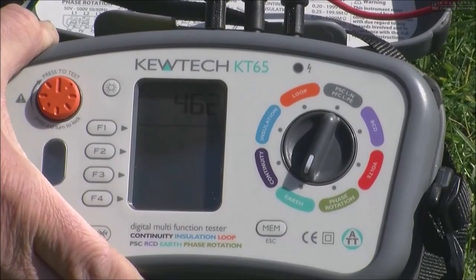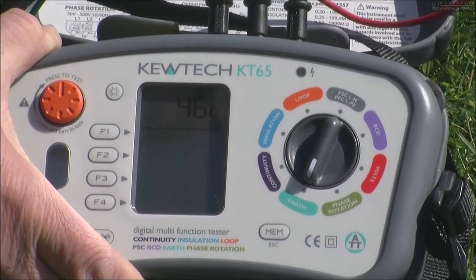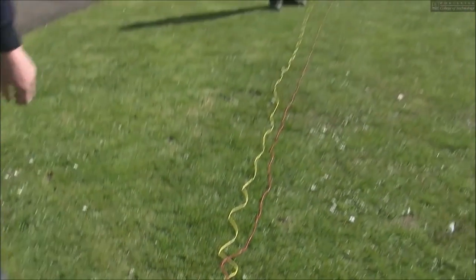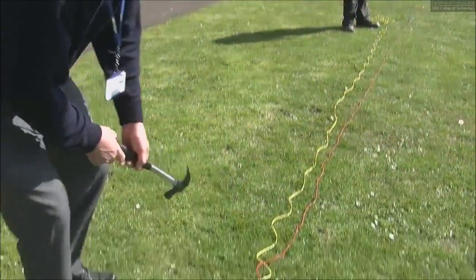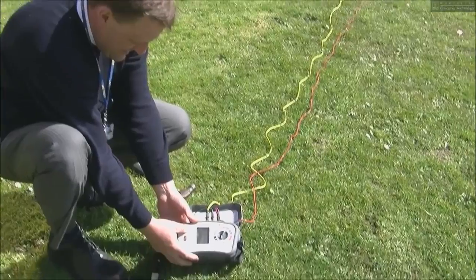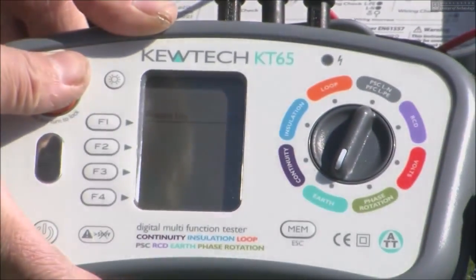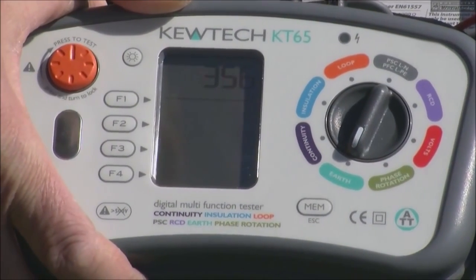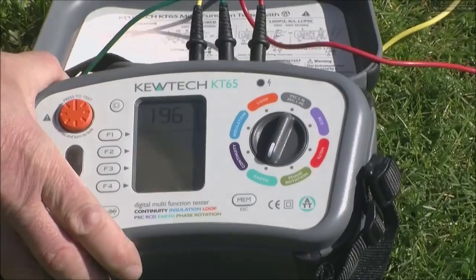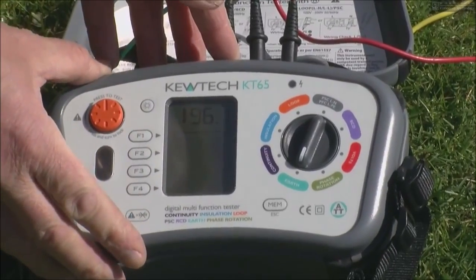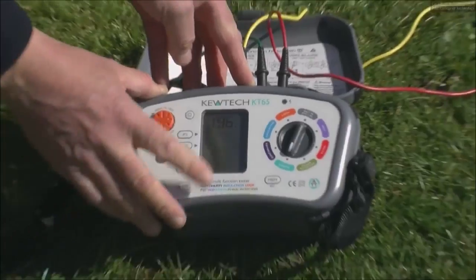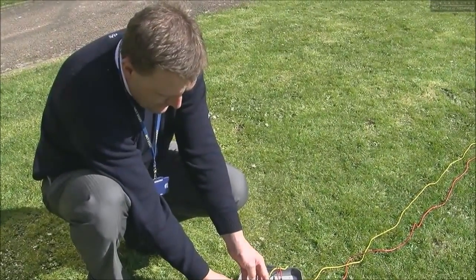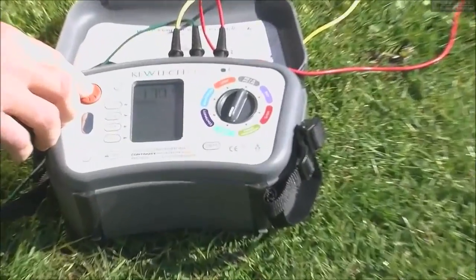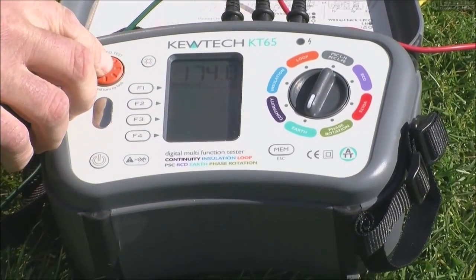You see, we've knocked the earth electrode in approximately 30 centimetres, and the readings are starting to come down now. We're at 462 ohms. Ideally, we want this figure to be less than 200 ohms. Getting less and less. We're now in at 70 centimetres, and you can see the value is below the 200 ohms, which we're after. We'll knock the earth electrode as far as we can, and see what readings we can get from this soil. 174 ohms. That's the lowest we're going to get.